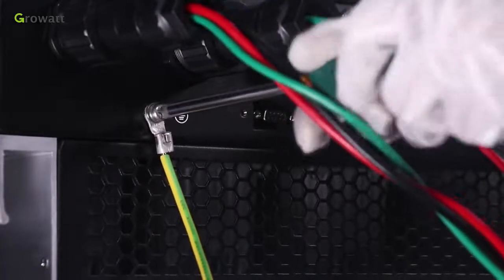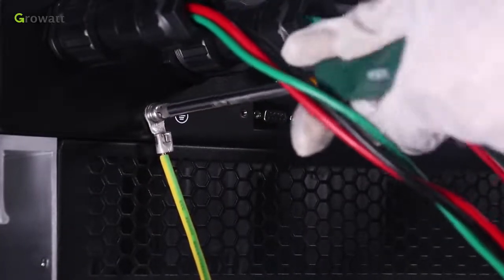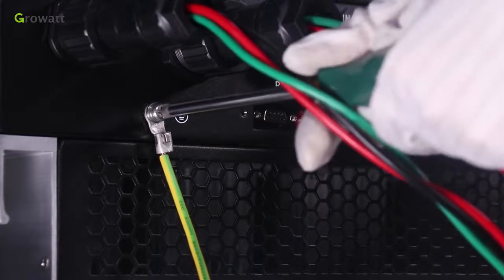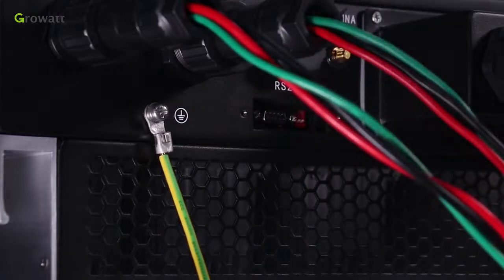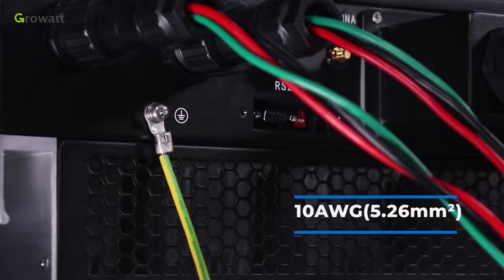Grounding connection. SPA series must be grounded by cable. The grounding point is showed as follow and the minimum grounding cable wire diameter is 10 AWG 5.26 square millimeters.